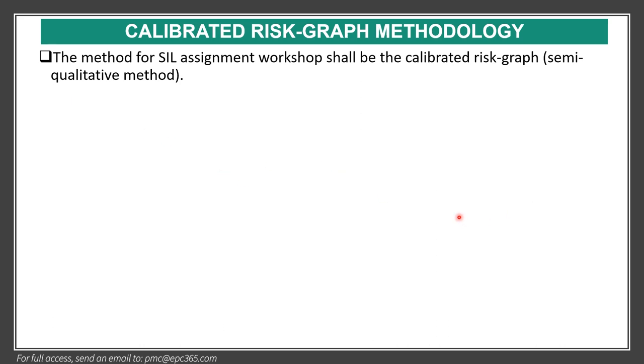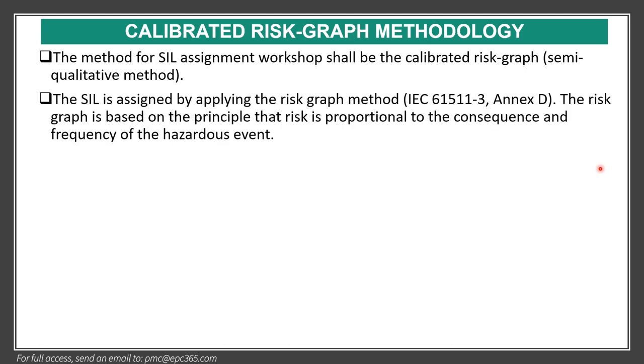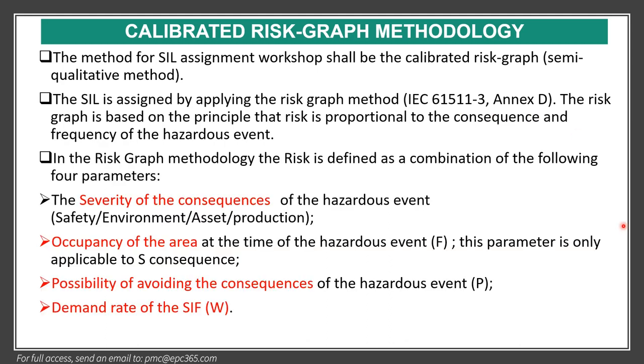The calibrated risk graph is a semi-qualitative method. It is based on IEC 61511, Annex D. For the risk graph, we have to get agreement about safety, environmental asset, and production. Key parameters include occupancy of the area (F), the possibility of avoidance of consequences (P), and the demand rate of the SIF.